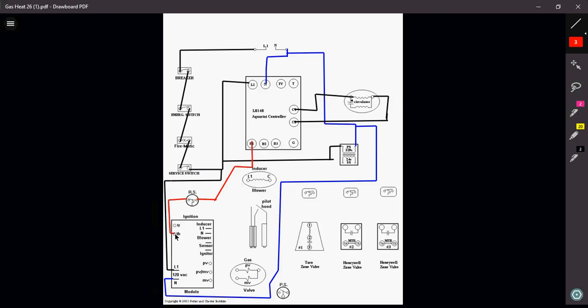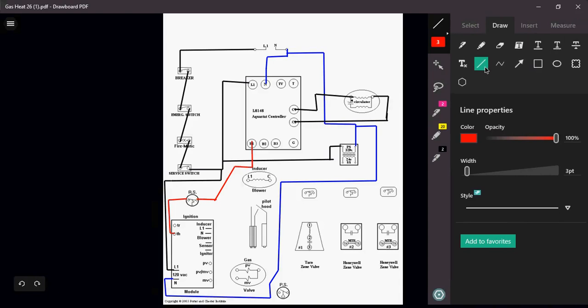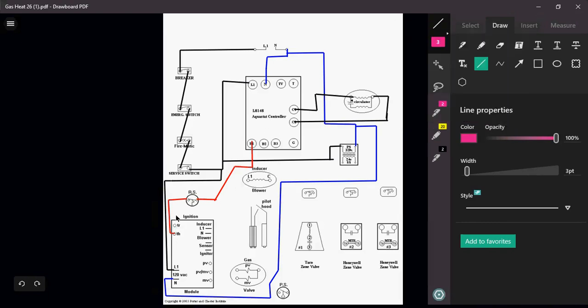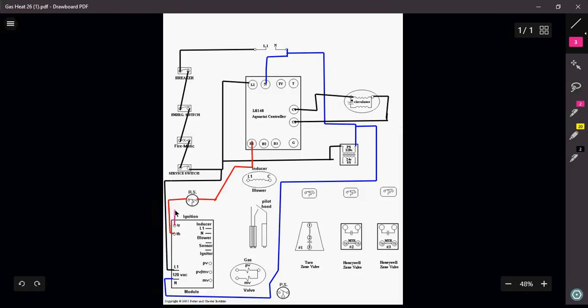In order for me to do that, I have to go through my rollout switch first before I go into my ignition module. That's my safety to take out my module in the event of an unsafe situation. So out of my TH, I'm going to go to my TR, and I'm going to just simply go back to my B3. So that circuit is now complete.